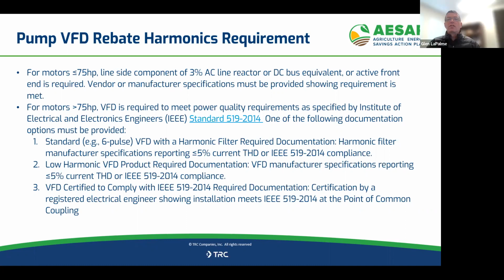There's a number of ways you can reduce your total harmonic distortion below 5%, and capacitors are one of them. For tier 1, where they're still offering the standard 6-pulse VFD, you have to install the filter either in the panel or in a separate panel adjacent to the VFD, and that will meet the line side compliance for IEEE 519.